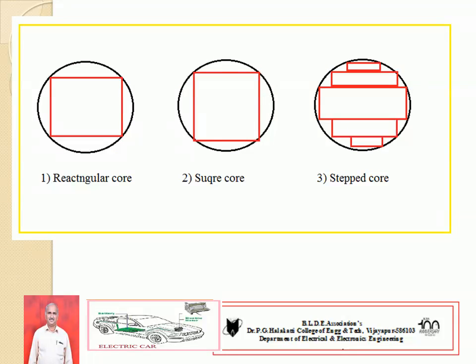The diagram shows different types of cores used in transformers: number one, rectangular core; number two, square core; number three, stepped core — which may be two-stepped, three-stepped, or four-stepped. You can go for multi-stepped cores. One important thing to remember: the two-stepped core is also referred to as the cruciform core. D is the diameter of the circumscribing circle, and by using D we can estimate the area of the circumscribing circle, that is π D² / 4.